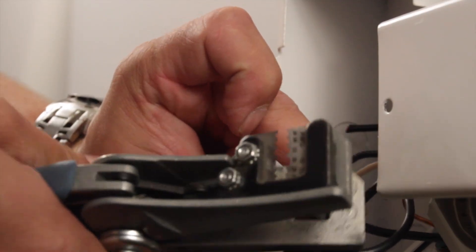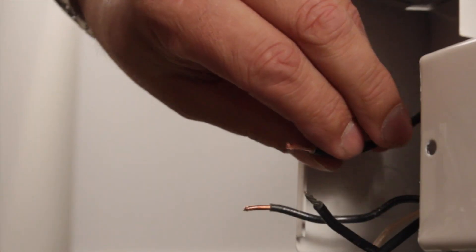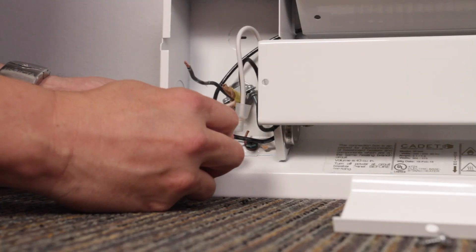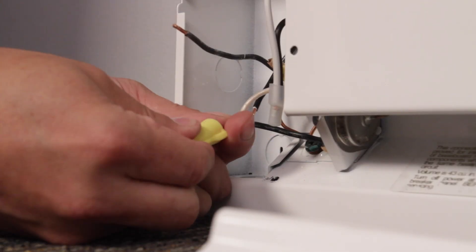Now strip the wires with wire strippers. You want about a quarter to a half inch of bare copper wire exposed. Connect one black wire from the heater to the white wire from the wall. It does not matter which wire you hook up first.